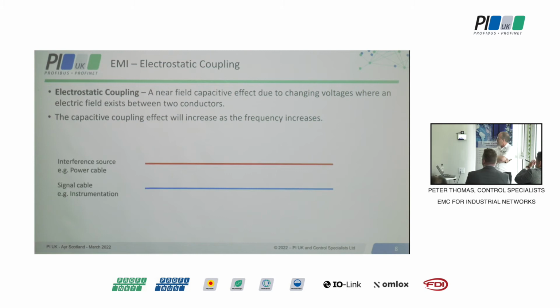So what are these two terms? We've got two conductors here. The red one is a power cable - maybe a single conductor in a three-phase installation, could be 240 volts, just some kind of interference source. In its vicinity is a blue cable, which could be any kind of signal cable - Profibus, Profinet, a thermocouple - a sensitive bit of kit. Imagine that red conductor is live, but there's no current flowing through it yet - we've just powered the supply. What we've created there is a capacitor: two metallic conductors separated by some insulation.